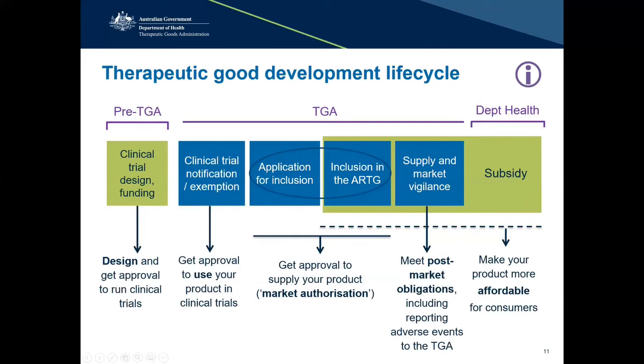If the application is successful, the medical device can then be imported into, supplied in, or exported from Australia. There are then post-market obligations on the part of the sponsor. That would include ensuring that the device continues to meet all regulatory requirements, reporting adverse events to the TGA, and also ensuring that advertising for the device is compliant with the Therapeutic Goods Advertising Code. And lastly, there are also various subsidies available from the Department of Health to assist with making products more affordable to consumers.